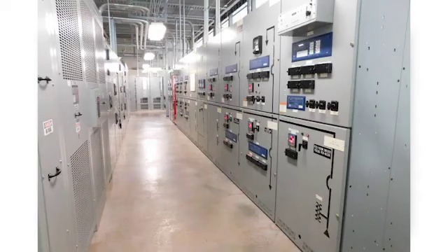The upper level, as you walk into the plant, you'll enter the main substation. We have a dual feeder configuration. We're connected to PSE&G, the electric utility, by two 13 kV full load capable feeders, so we can run on one alone. And that's how we normally operate: one feeder closed, the bus tie closed, and one feeder open on hot standby.